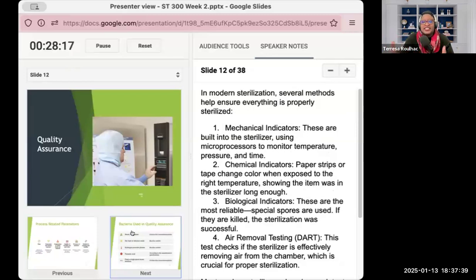In modern sterilization, several methods help ensure everything is properly sterilized. We have mechanical indicators, which are built into the sterilizer. They use microprocessing to look at the temperature, look at the pressure, and make sure the time is correct. Chemical indicators are what you see in your set. Again, trust the process. You have a paper strip or tape, and it's going to change color once parameters have been met. We're not saying that we can 100% guarantee sterilization, but we can say that the parameters have been met for the sterilization of these instruments.